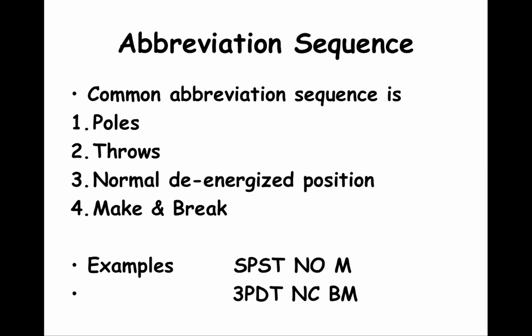When ordering relays, the common sequence for listing characteristics is: first the number of poles, followed by throws, followed by normal de-energized position, and then any make or break characteristics needed. For example, SPST-NO-M is a single pole single throw normally open relay that will make a circuit when energized. Another example is 3PDT-NC-BM, a three pole double throw normally closed relay that will break and make circuits when energized.